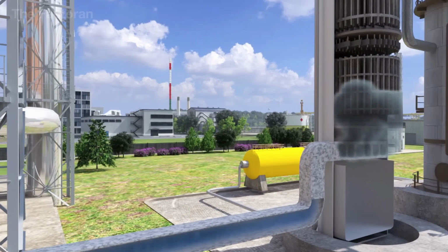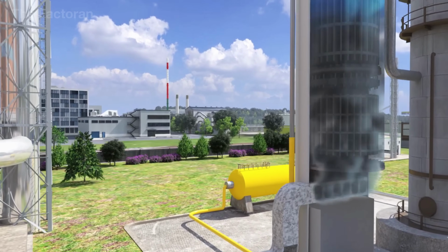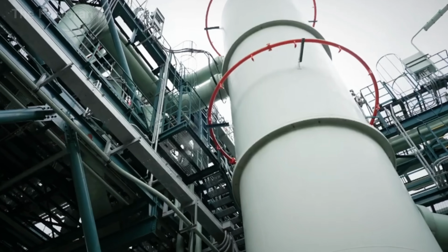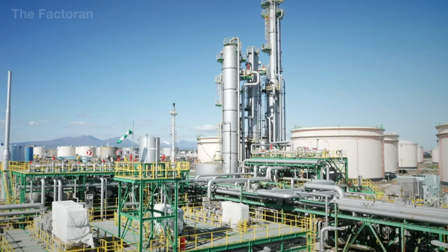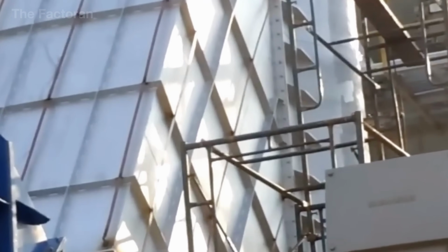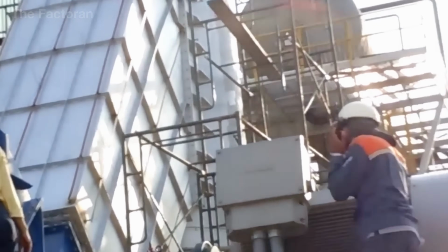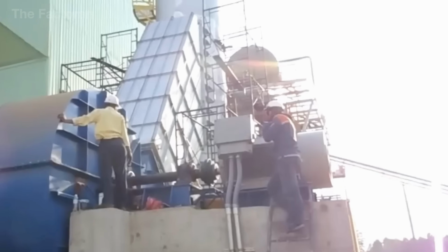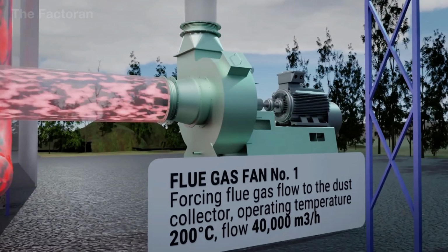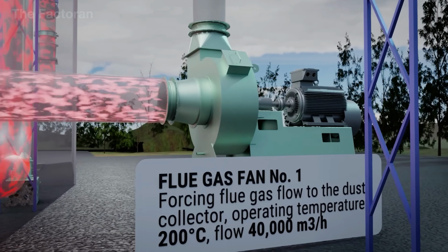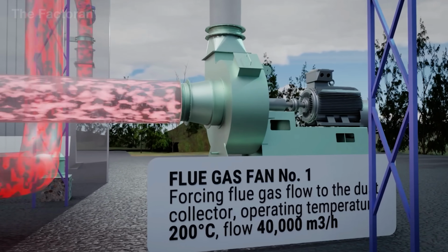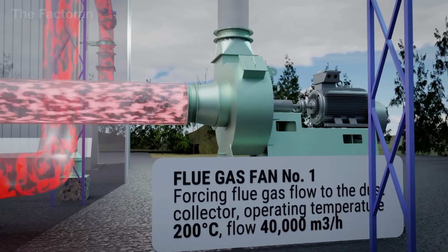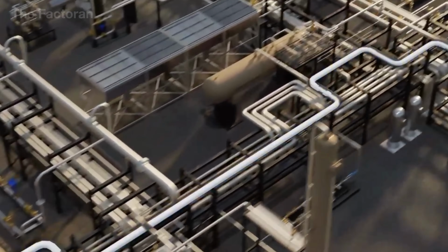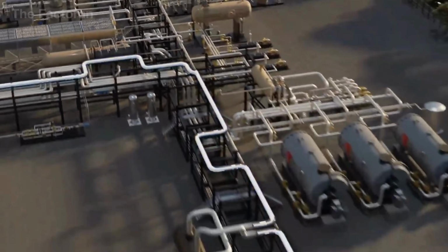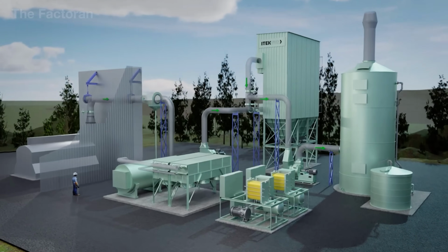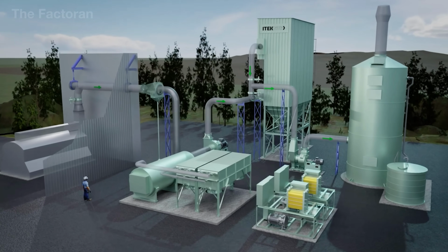Inside the ducts, temperature and pressure sensors constantly monitor for any fluctuations. At the end of the duct network is the industrial induced draft fan, a negative pressure blower that keeps the airflow stable throughout the system. Each fan can operate at around 200 degrees Fahrenheit, handling more than 40,000 cubic meters of air per hour. Powerful enough to draw gases from multiple sources and push them toward the dust separation, SO2 removal, and NOx reduction stages that follow.